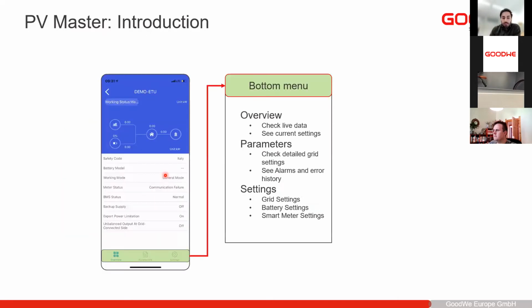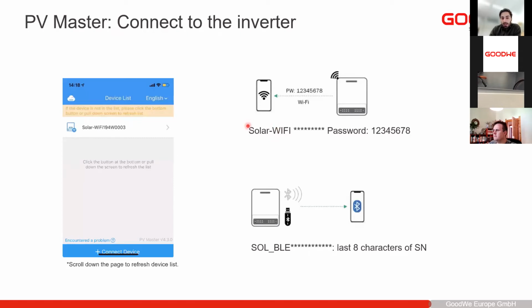Yes. So when you connect, let's say you use the Wi-Fi module, you have the Wi-Fi module connected to the inverter, then you go into your phone or device and search for the Wi-Fi. It's usually called solar Wi-Fi with the last digits of the serial number of the inverter. So if you're commissioning several inverters, you can distinguish which one you want to connect to by the end numbers in the Wi-Fi. So there you have it corresponds to the serial number. To log into the solar Wi-Fi or the Wi-Fi of the inverter, the default password is 12345678. So 1, 2, 3, 4, 5, 6, 7, 8.